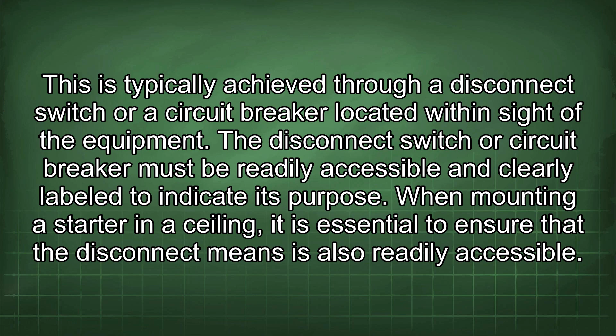When mounting a starter in a ceiling, it is essential to ensure that the disconnect means is also readily accessible. This might involve installing a remote disconnect switch at a more convenient location, such as near the control panel or at floor level. Consider the implications of working on energized equipment. In general, it is always safer to de-energize equipment before performing any maintenance or repair work.